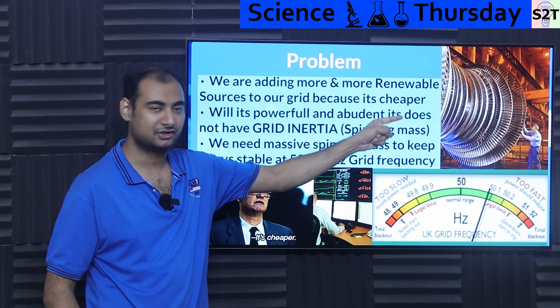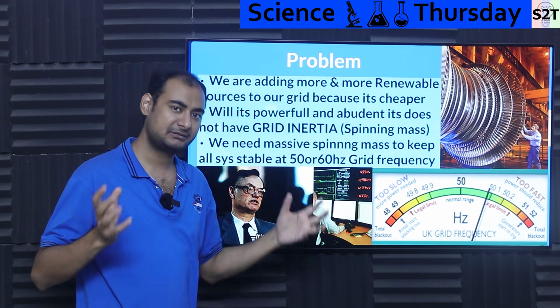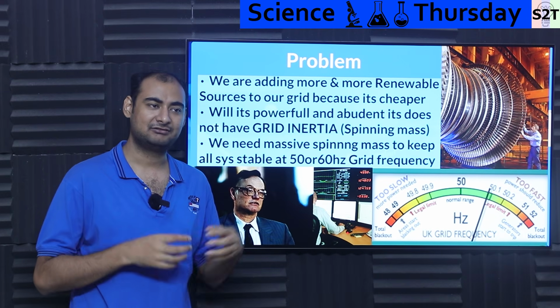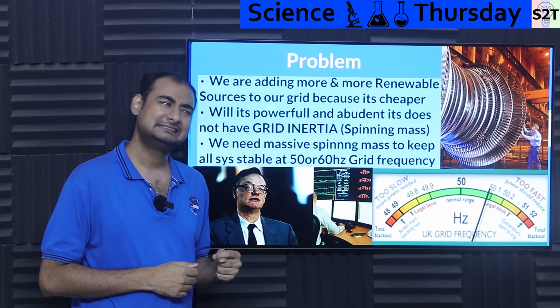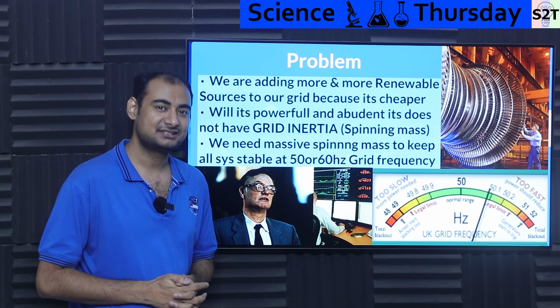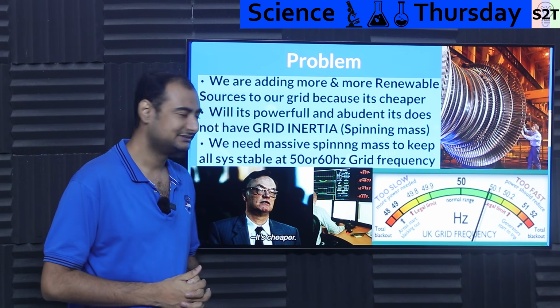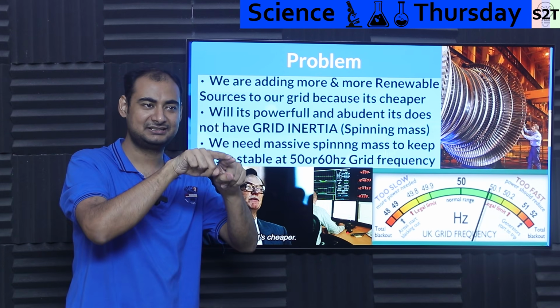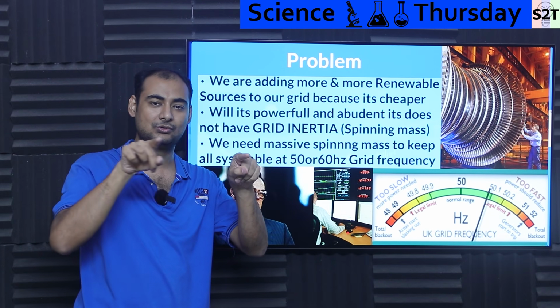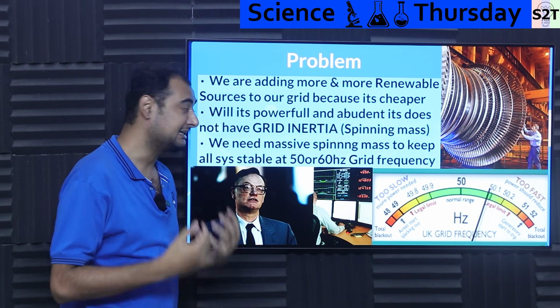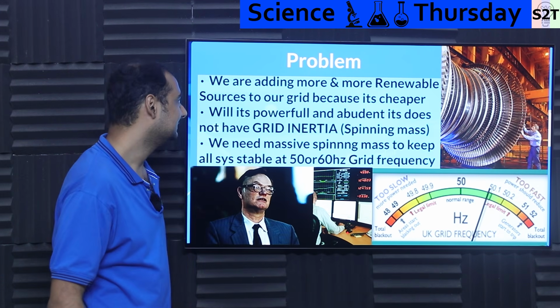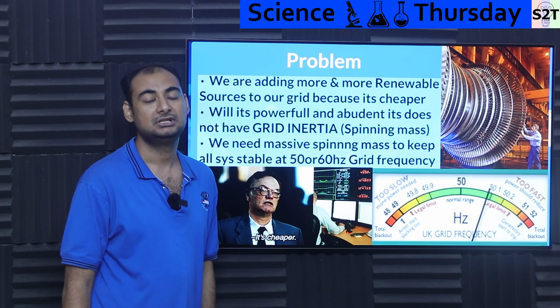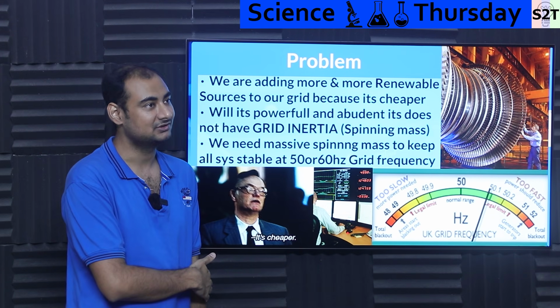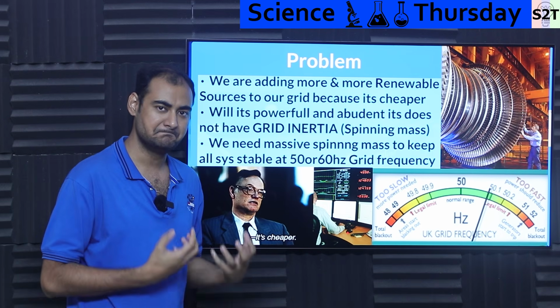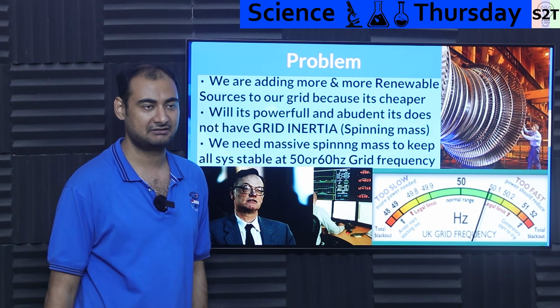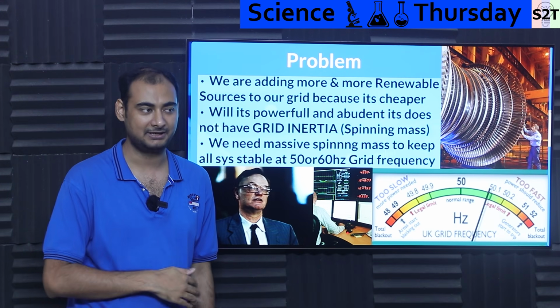And it requires inertia. It requires massive objects spinning. The more massive, the more stable the grid becomes. Because if you have a 100-ton object spinning and you jerk load into it, it will notice it. If you have 600 tons, it's like, bruh, I ain't got time for this. So fundamentally, that's what you want. An induction spike will happen like this, and you want your generator spike to happen like this. The slower it is, the better it is. So you want mass, and that mass has to be spinning, so it's actually coupled. That's the core problem. And yes, if you start to directly dump a lot of solar and wind into the grid, you will kaput the grid because it will have too much power but not an adequate amount of mass. So this will start to go like this, and generators will trip left and right. So basically your whole substation grid will be like, no, blackout.